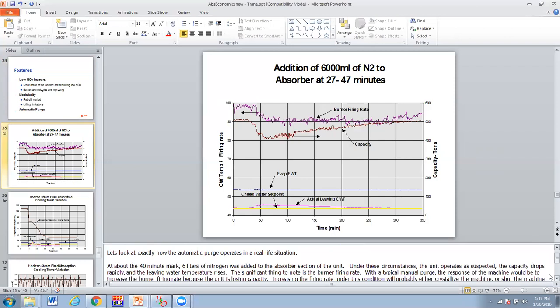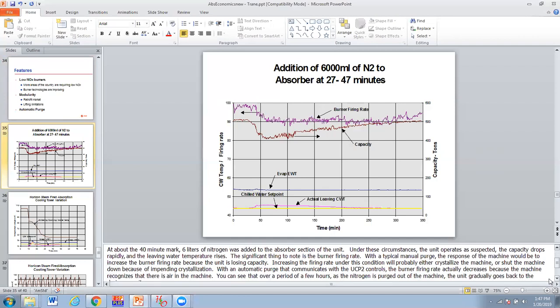This shows how the automatic purge operates in a real life situation. At the 40-minute mark, 6 liters of nitrogen were injected into the absorber section of the unit to simulate a leak. Under these circumstances, the unit operated as expected. Capacity drops rapidly. So here's capacity. We were up here, we inject this, and capacity bottoms pretty quickly. And leaving water temperature rises. Here's the actual leaving water temperature. We were down here on set point, and you see we went up and stayed up for a while.